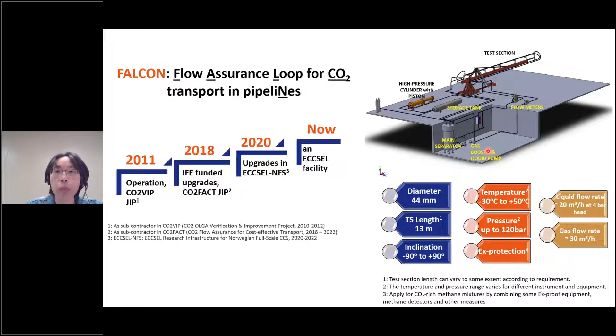For most components in the loop, we have a temperature rating from minus 30 degrees to plus 50, and pressure up to 120 bar. This loop also has EX protection, combining some EX proof equipment, leak detectors and other measures. So this loop can run with CO₂ rich mixtures. The liquid pump can deliver, for example, 20 cubic meters per hour at 4 bar head, and the gas booster can deliver 30 cubic meters per hour. So this is the loop.